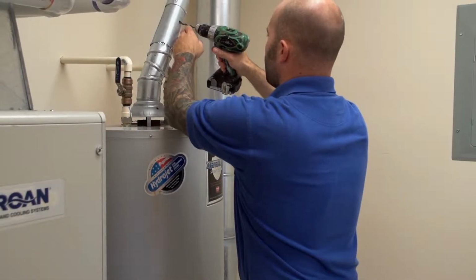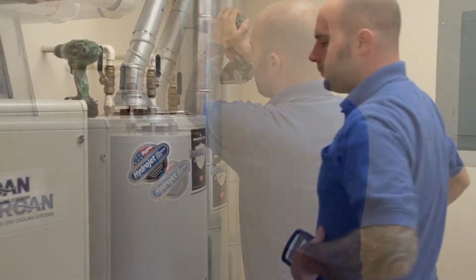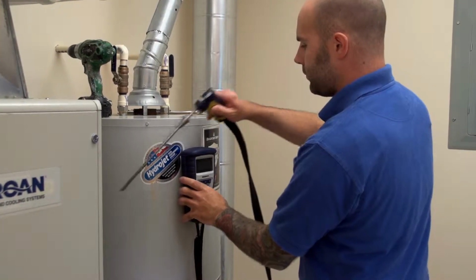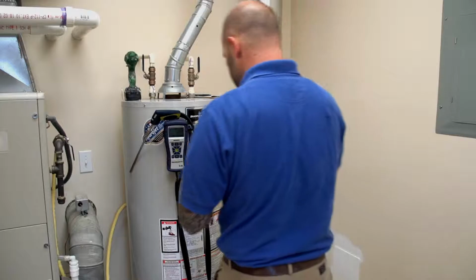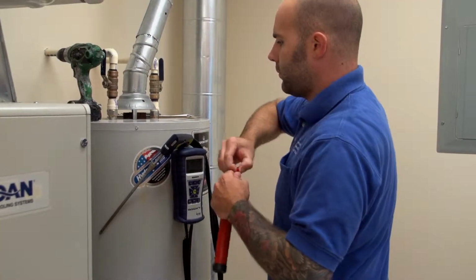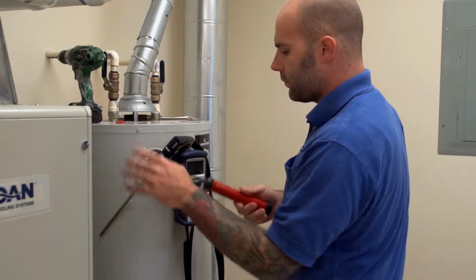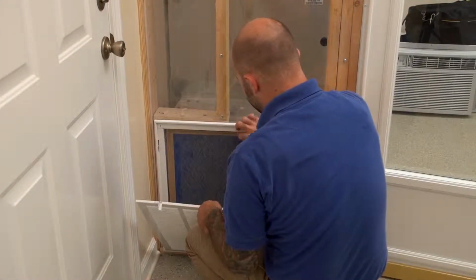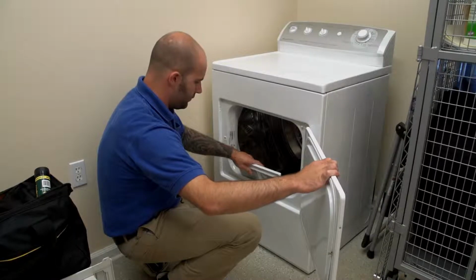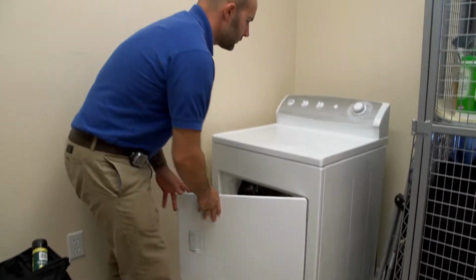Proceed with the CAS setup. As an RIT specialist, you will not be responsible for testing the CO content. Be sure to reseal the test hole after completing the worst-case CAS test. Organize and set up your tools. At this time, check the condition of the air handler filter and remove it for worst-case test. If a dryer is present, check the lint filter and inspect the venting system for problems.